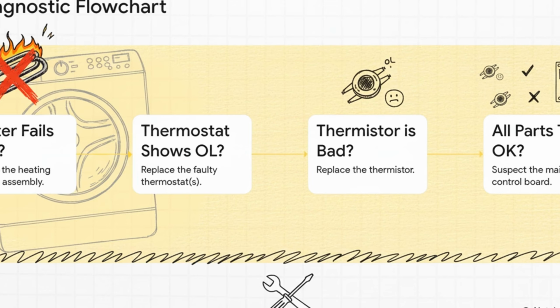If the heater failed any of our two tests, you just replace the heating element. Simple. If the heater's good, but a thermostat is bad, you replace the thermostat, though honestly, they usually come with a new heater anyway. If the thermistor is bad, replace that. And only, and I mean only, if every single one of these other parts tests perfectly, should you even start to think it might be the main control board.